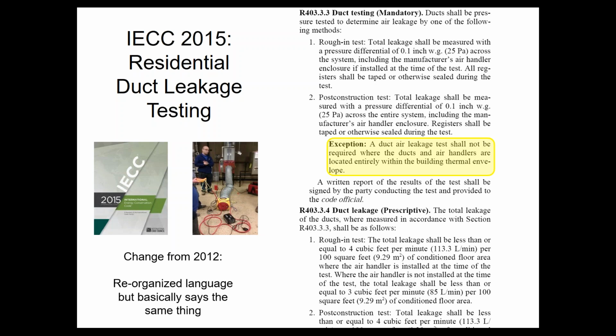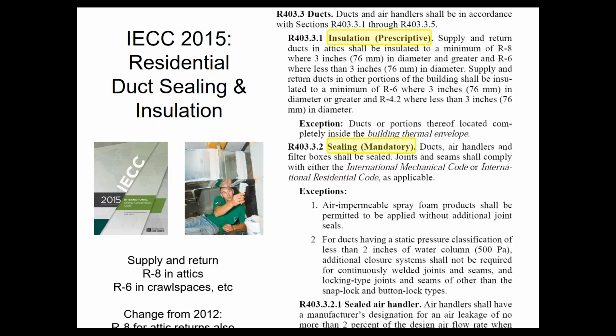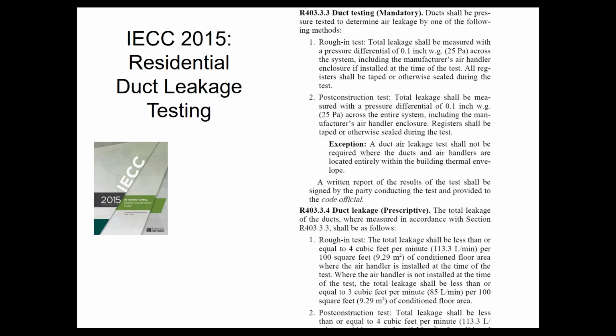Todd asks if the exception applies to the actual mandatory sealing. No. If I go back to the sealing, it is required no matter what. You have to do the duct sealing. You only have to prove you did a good job of the duct sealing if your ductwork goes outside the thermal envelope. Otherwise, it'd be a visual inspection.